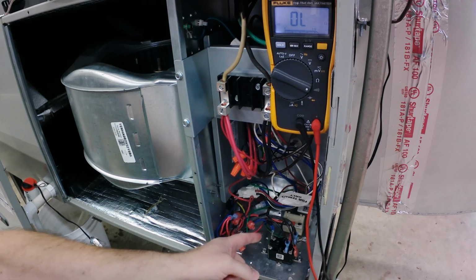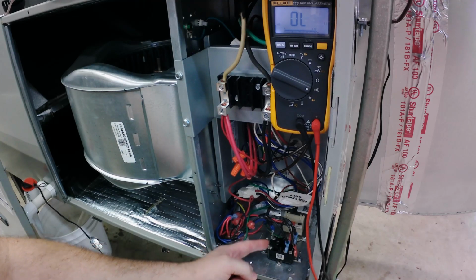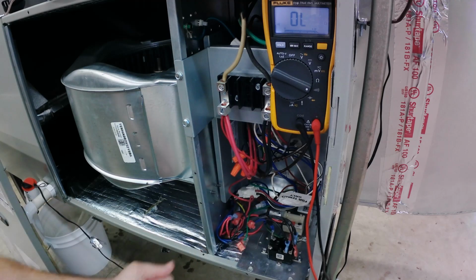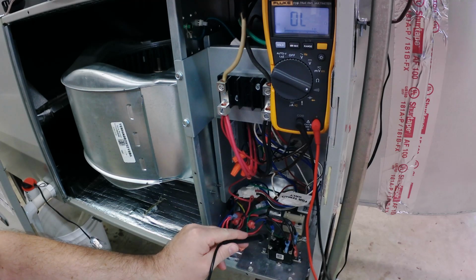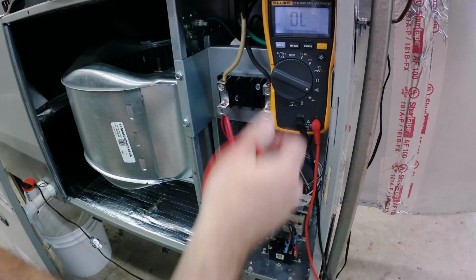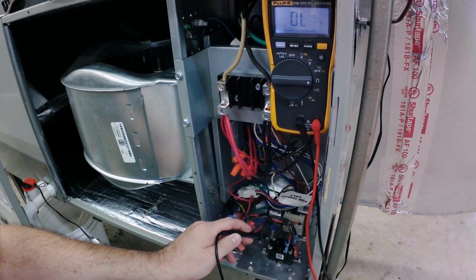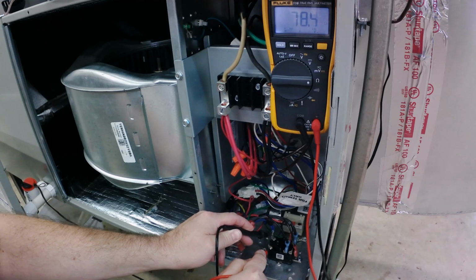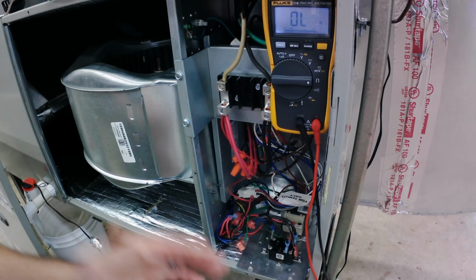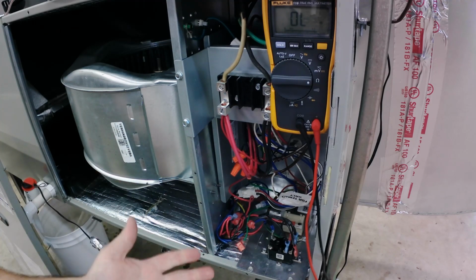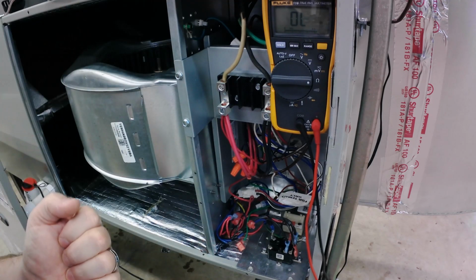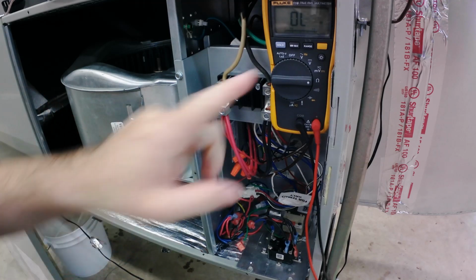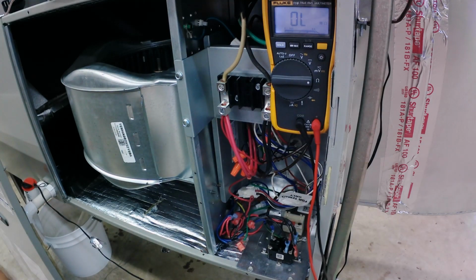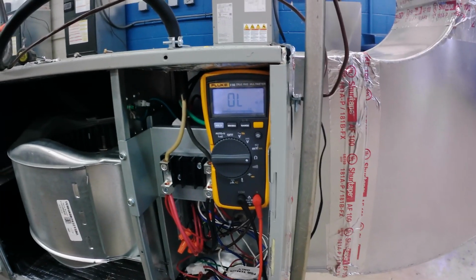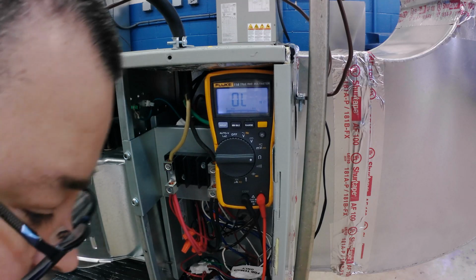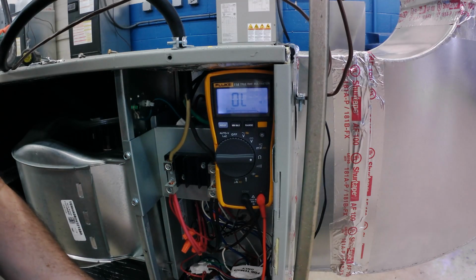So while you're there checking 24 volts on those two terminals, go ahead and real quick take one of those wires off and ohm out the coil. So I did the continuity and you can hear it beeping. If you just switch it to ohms, I'm going to get the same thing, 78, 79 ohms. For me personally, ohm values are in my head, I make it real simple. If I see OL like you do here on the screen right now, let me turn that up there.